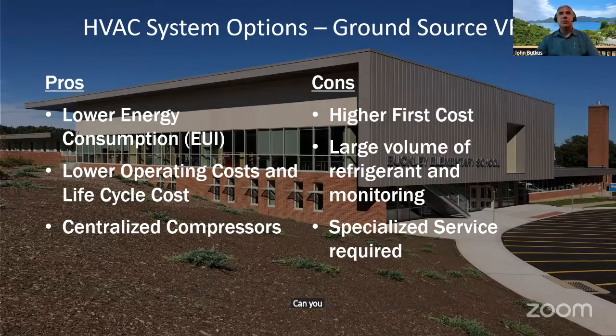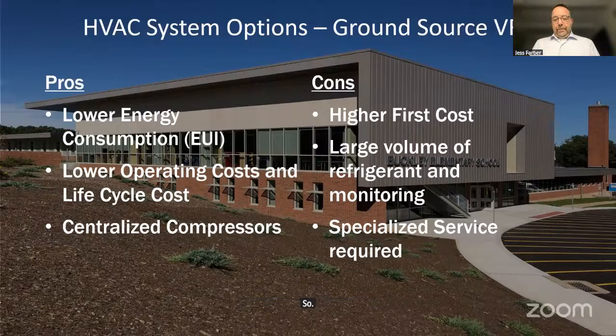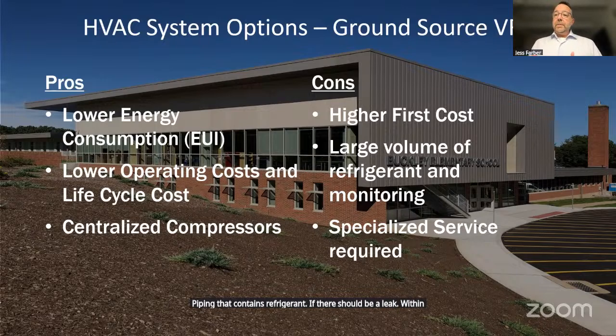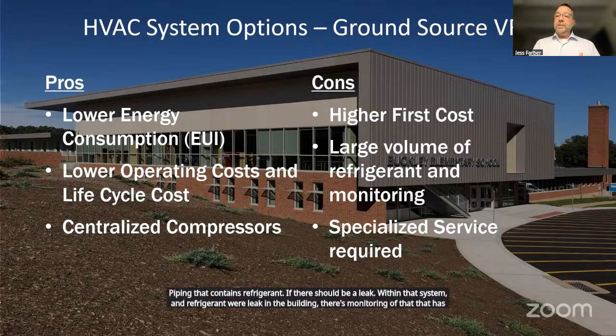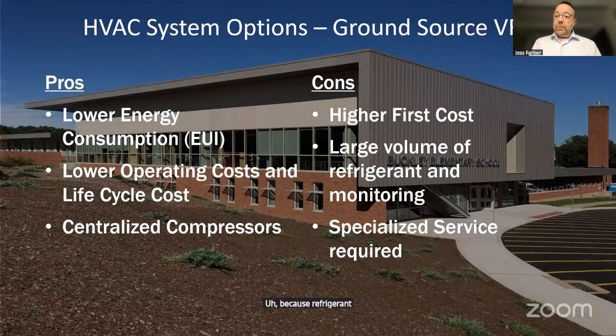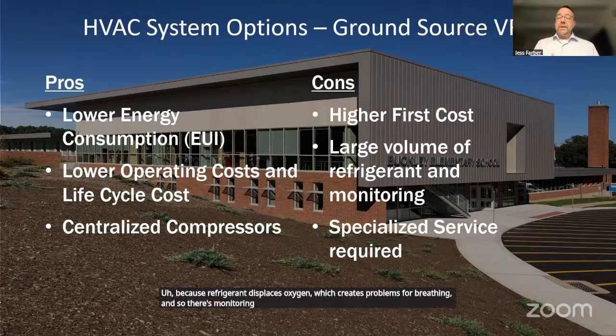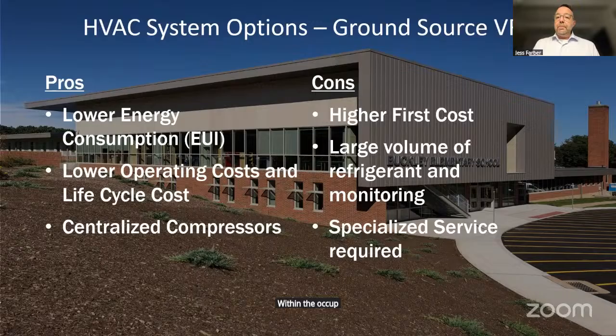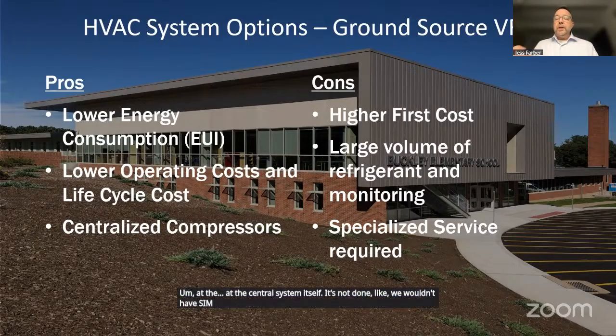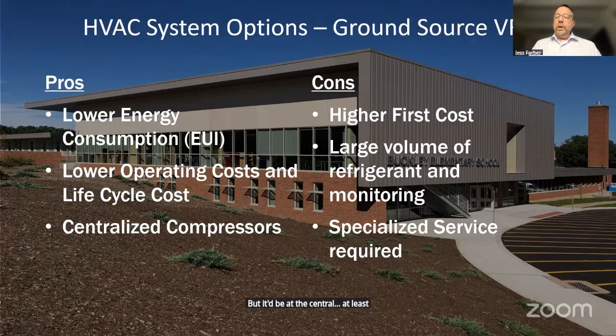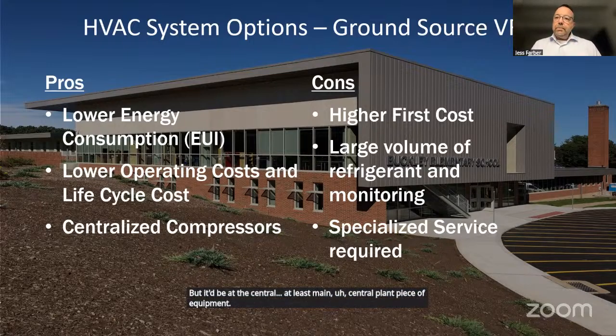Can you define the term monitoring? This system has refrigerant piping that connects all of the interior heating and cooling units, a large network of piping containing refrigerant. If there were a leak within that system and refrigerant leaked into the building, monitoring has to happen within the spaces because refrigerant displaces oxygen, which creates problems for breathing. That monitoring occurs at the occupant levels to make sure it hasn't leaked, but it's generally done at the central system itself. We wouldn't have sensors all over the building, but at each main central plant piece of equipment. Does that help answer your question?